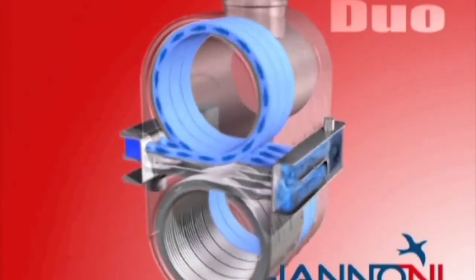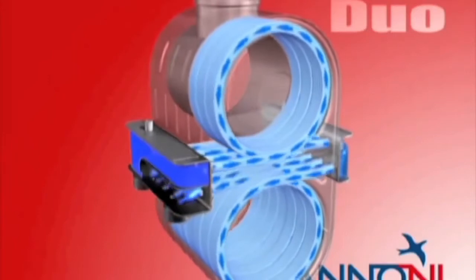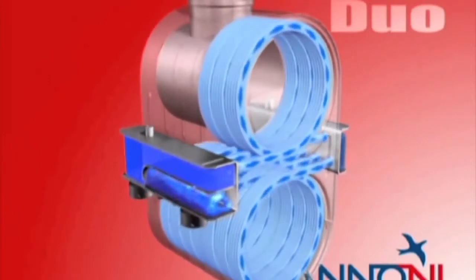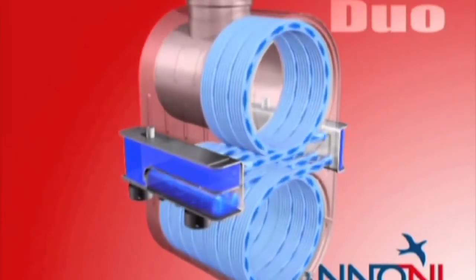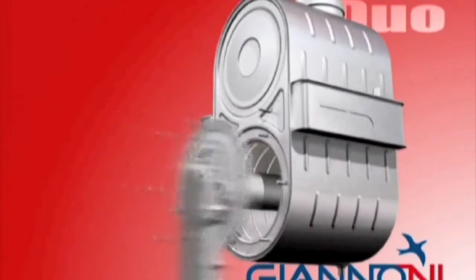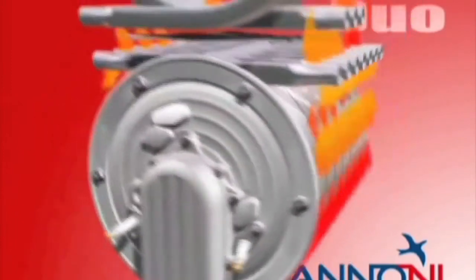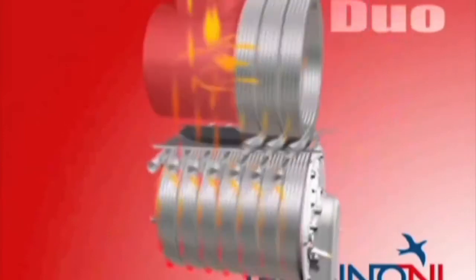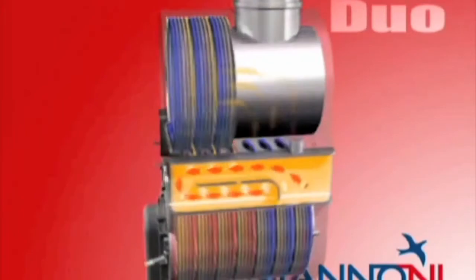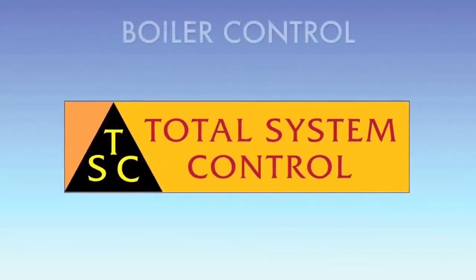The unique water baffle system directs water through the heat exchanger to provide maximum heat transfer with minimal water pressure drop. The system's cold water return is directed through the back section and upper section, absorbing all the energy from the combustion process. The water is then directed through the front section of the heat exchanger, where the heated water is delivered to the connected system. To illustrate this unique design, we have added the burner and removed the cabinet to show how the water is heated. Both the combustion gas and the water move through the heat exchanger, which provides maximum heat transfer in a very small space.